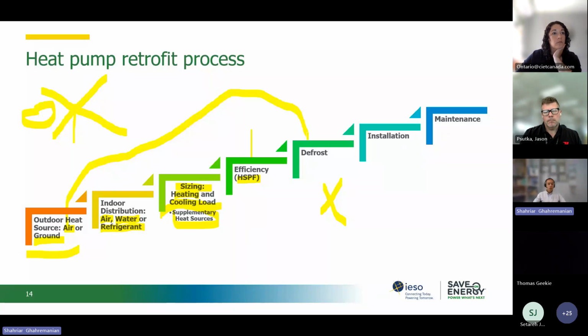But the heat pumps during the heating season need to do the defrost, actually. During this time, the heat pump is working, but it doesn't supply any heating to the building. So we need to consider that, and that is why the location of the installation of the heat pumps becomes important. It's not like the air conditioning system that we put wherever we want and then say, okay, that's enough, because we cover them during the winter. These machines need to run during the winter season, so they need to be above the snow level, actually. So we cannot put them right on the ground. And also, if we can have an enclosed area around it, that also helps them perform better and improve their efficiency. And then we need to consider the maintenance, how we want to maintain them, how we want to clean them and check the refrigerant and the performance as well, actually.